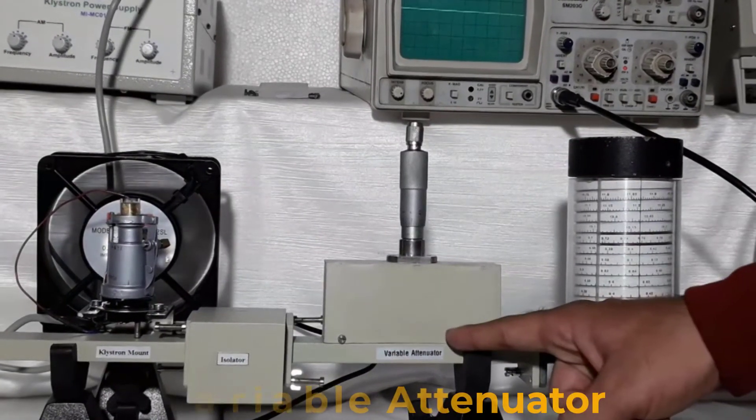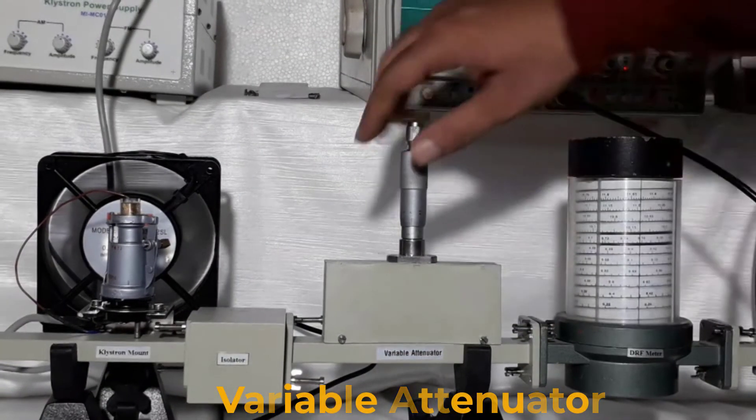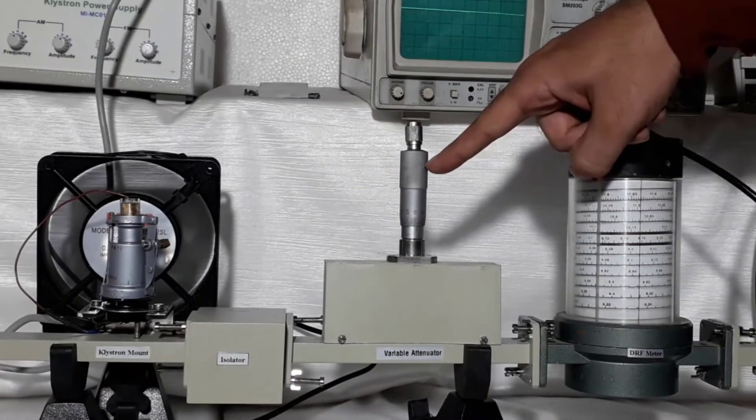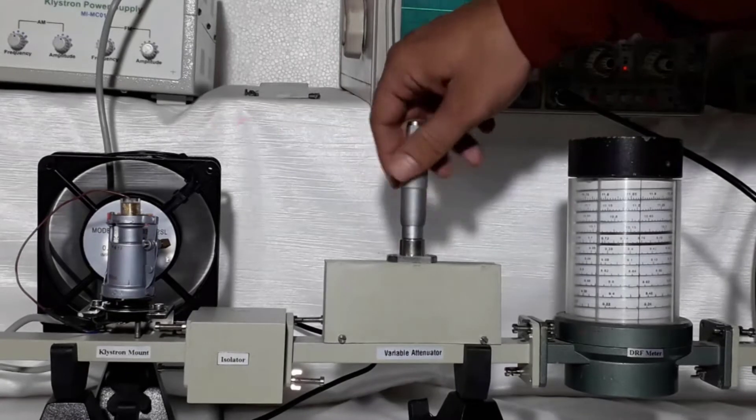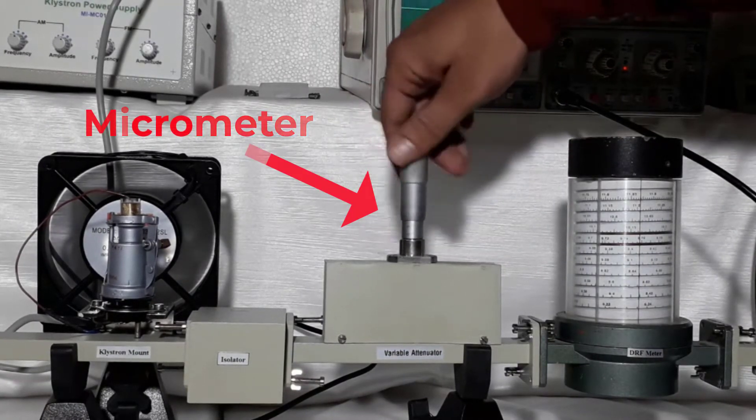Variable attenuator is connected after isolator. This is used to attenuate power of microwave signals. Initially, variable attenuator is set for no attenuation, that means micrometer of variable attenuator is completely open.